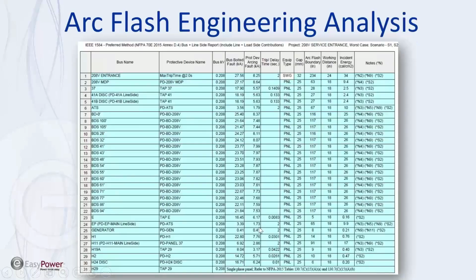So if you do a study, then you come up with tables like this, and the table shows the bus name, the protective device that's protecting whatever it is you're working on, and then it has the bus voltage, the fault current, the available fault current is on there. So let's take a look at some of these.